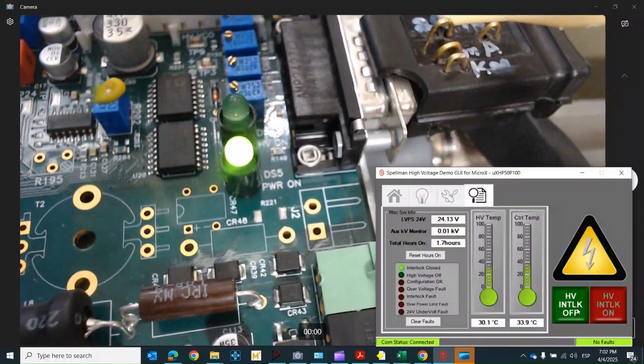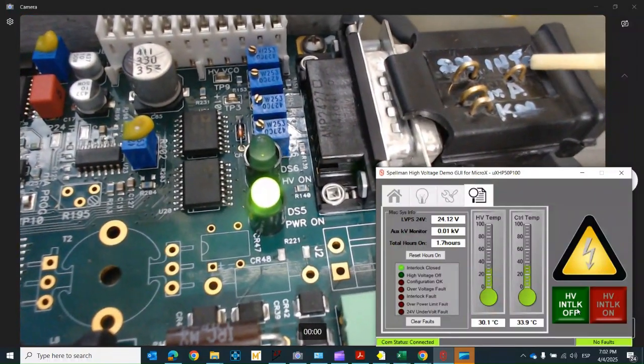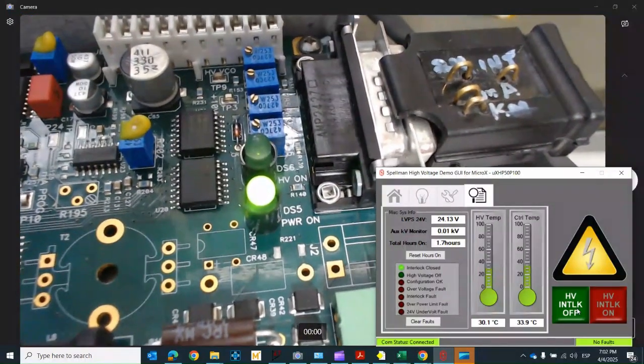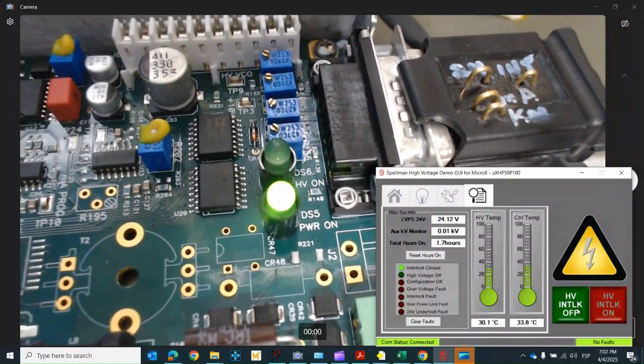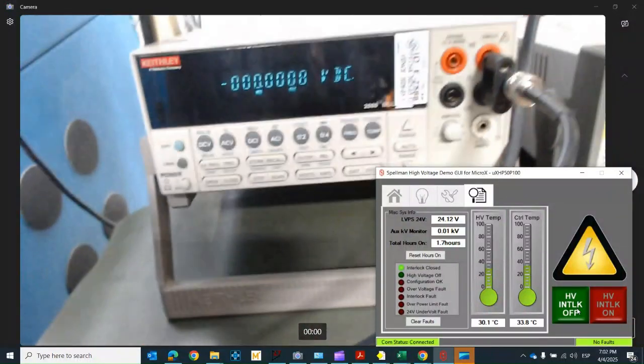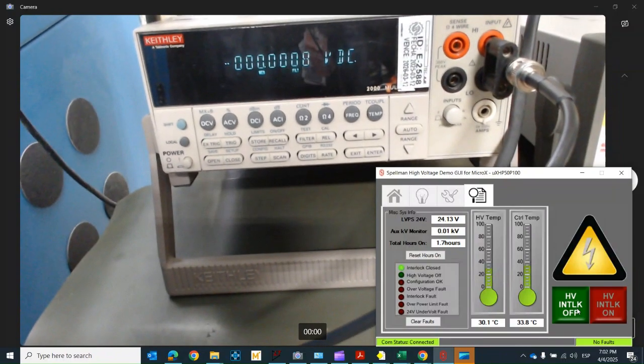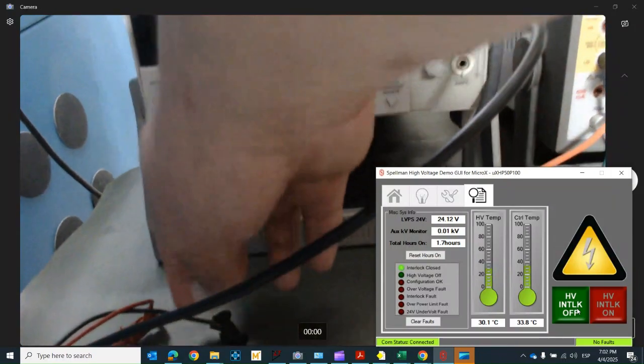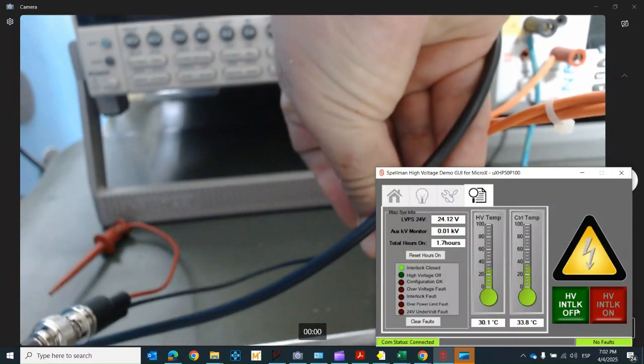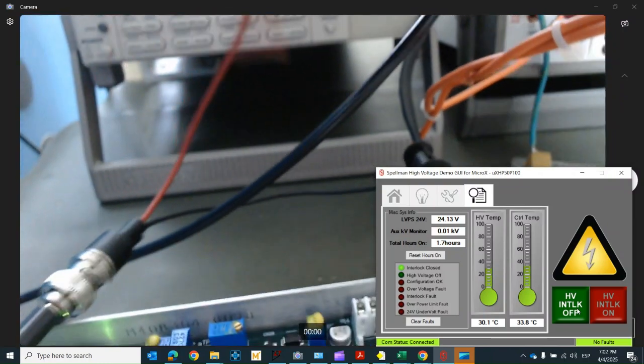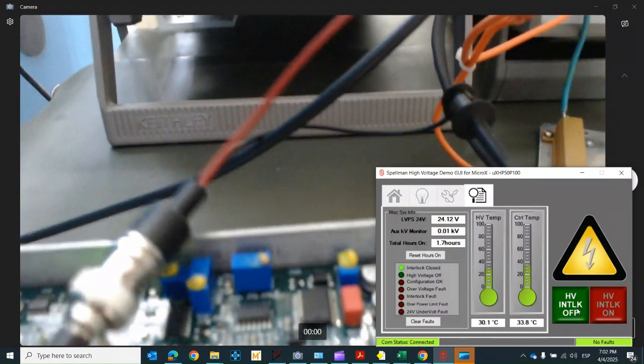At the 15-pin interface jumper, there are two signals of interest we will monitor. One of these is a 24V monitor signal that is located at the pin 13 of the 15-pin connector. Using the test point DMM, we will measure the pin labeled as 24V. This should be approximately 24V.